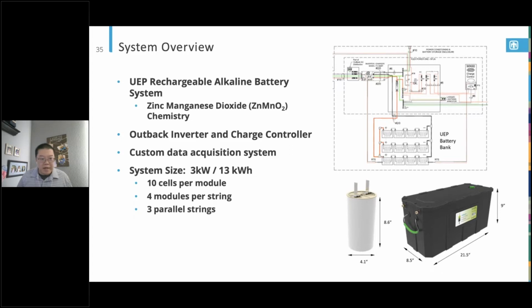The system consists of batteries, an off-the-shelf Outback FX series inverter, an MX series charge controller, and a custom data collection system assembled at Sandia using off-the-shelf equipment. The system is rated at 3 kW and 13 kilowatt hours, consisting of 10 cells per module, 4 modules per string, and 3 parallel strings.